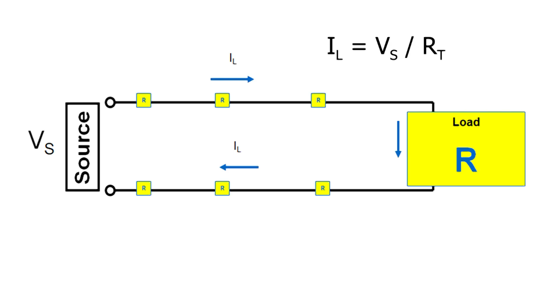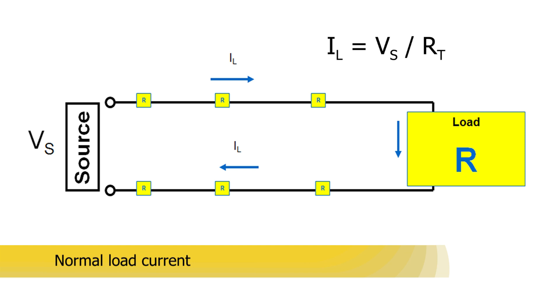The purpose of the fuse is to act as an electrical safety valve to protect equipment and components from all types of overcurrents, thereby minimizing damage. An overcurrent is either an overload, a short circuit, or a ground fault. The overload current is an excessive current relative to normal operating current, but still confined to the normal circuit path provided by the conductors, components, and loads, whereas a short circuit or ground fault flows outside the normal circuit path.